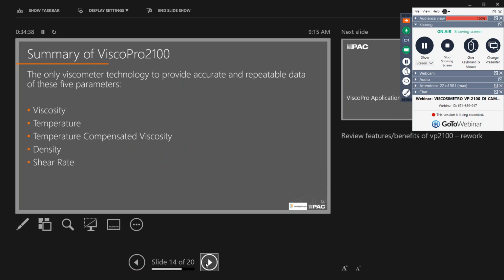So to summarize ViscoPro technology, it's got many benefits. It's rugged, it's reliable, it's self-cleaning, it's accurate, it's low maintenance, but you also get a lot of information from this device. We get the viscosity, right? It's in centipoise, which is a dynamic viscosity measurement, but we can also provide it in other units of kinematic viscosity. You get the temperature with our built-in RTD. You get temperature compensated viscosity, so you can ensure that you have an accurate coat weight.